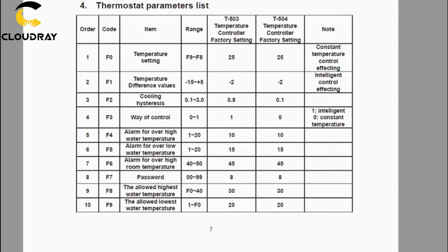I'd like to draw your attention to code F3, the way of control. There's two options here, 1 and 0, 1 being intelligent and 0 being constant temperature. Intelligent mode will cool the water to 3 degrees below room temperature, and this may be okay for some applications of this chiller, but when I'm using it with the laser, in my case in the workshop, temperatures reach over 35 degrees on a good day. And this would mean that the cooling would still maintain the temperature in the plus 30 degree range, which is not the best for my laser.